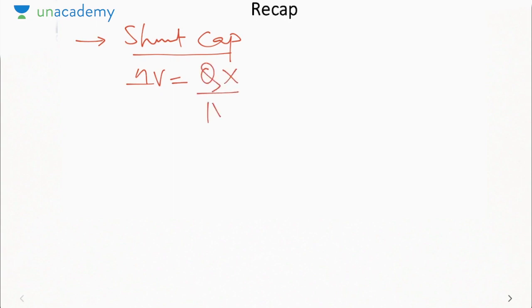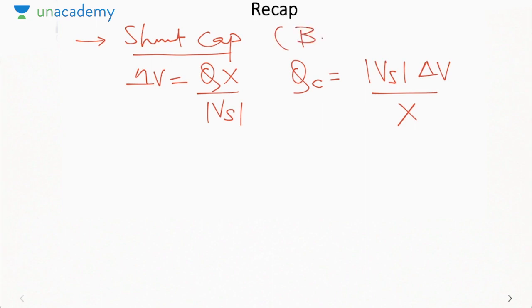We saw in the last lecture there are two techniques for voltage control. One was shunt compensation using a capacitor, and the other was shunt compensation using an inductor. So we saw in the shunt capacitor that delta V was Q into X by mod V, and the capacity required for the capacitor would be Vs into delta V by X. Delta V is the change in the voltage required. So it is used to boost the voltage, or increase the receiving end voltage.